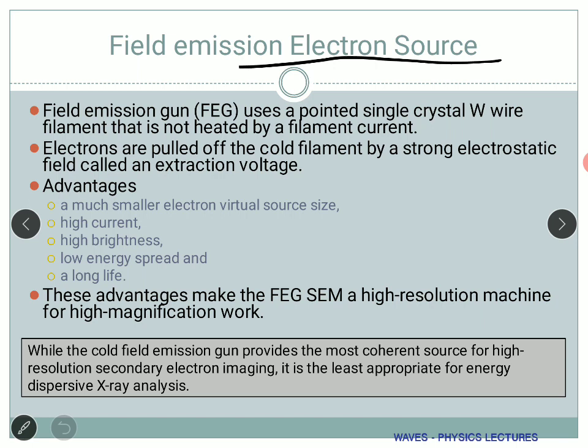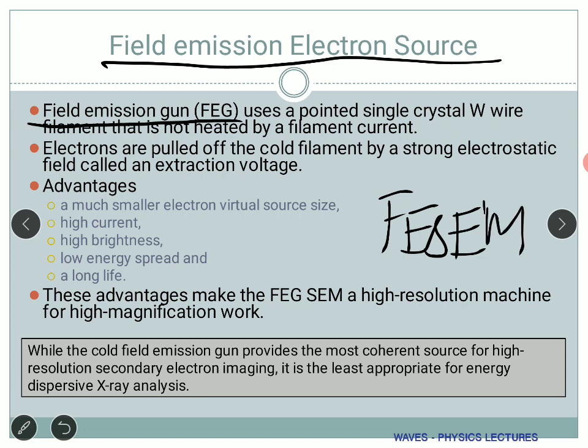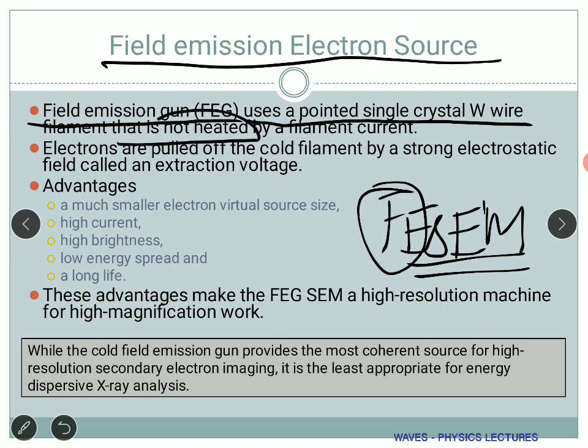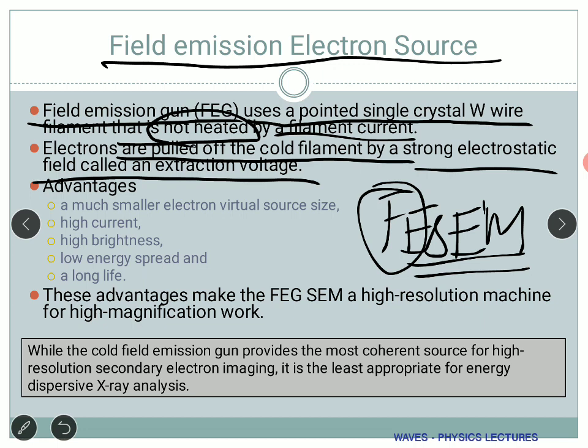Now for the field emission electron source, we apply a very high electric field to generate electrons. This is called FEG, and if you have come across the term FESEM, it stands for Field Emission Scanning Electron Microscopy. In FEG, it uses a pointed single crystal tungsten wire — the filament is not heated by filament current. The electrons are pulled off the cold filament by applying a strong electrostatic field called an extraction voltage.